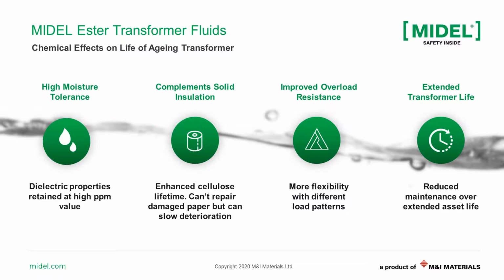That is why we can use these high values. The other thing about ester liquids is that they always like to collect and keep moisture. If it's inside the transformer, that means it would like to collect this moisture from inside the materials, like from the cellulose.